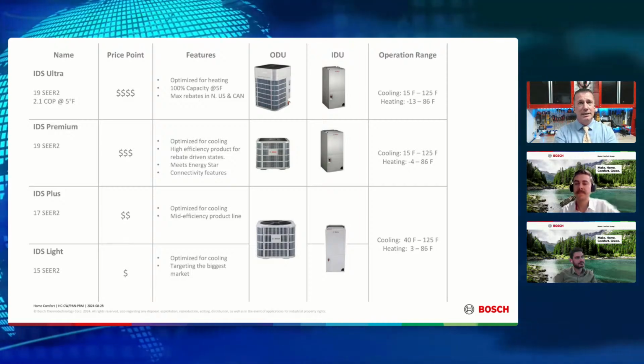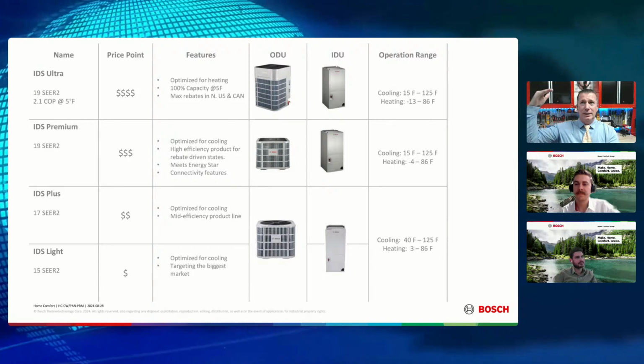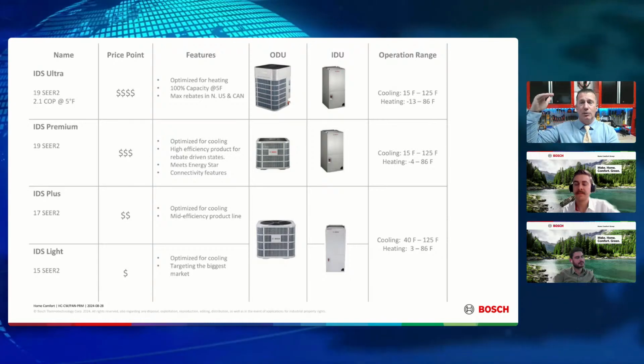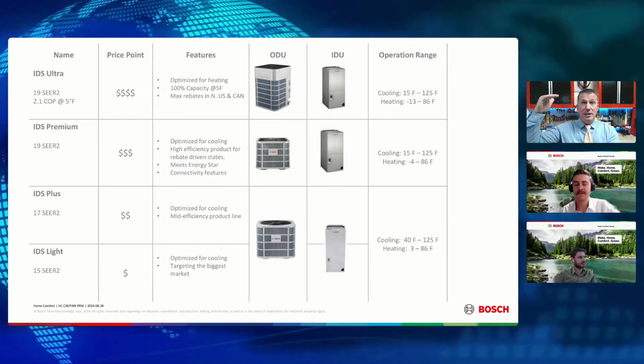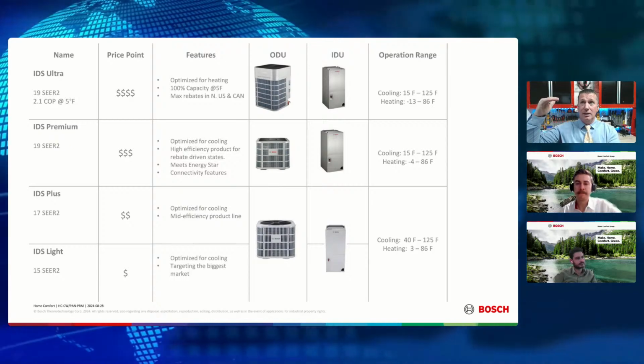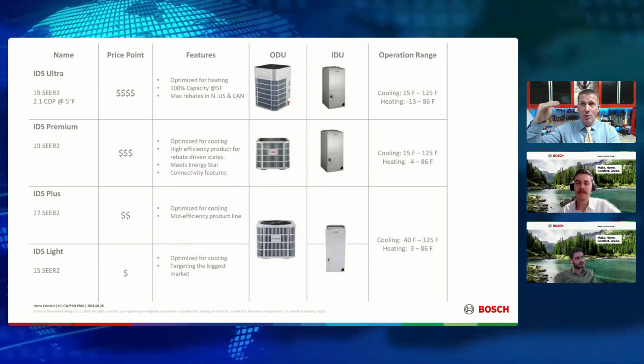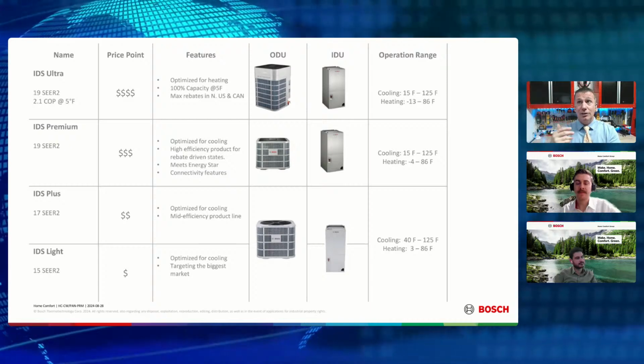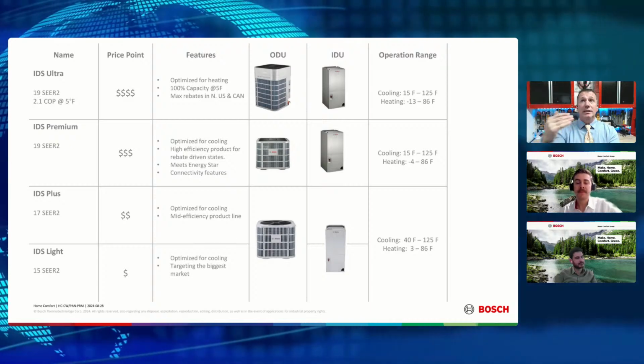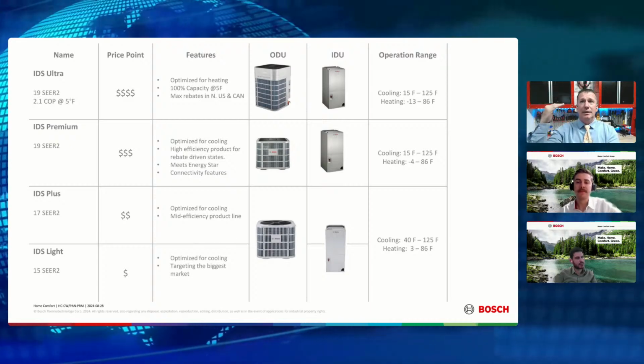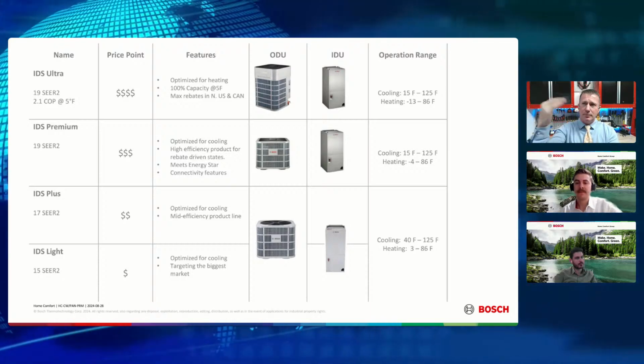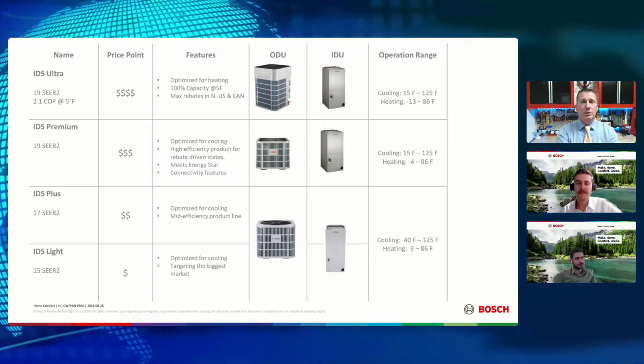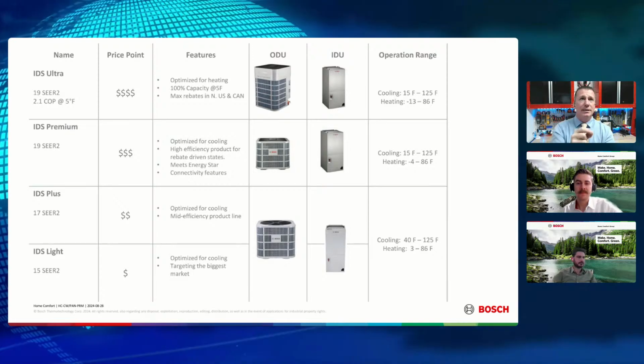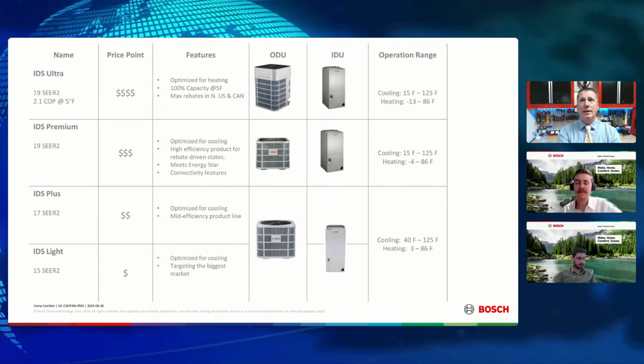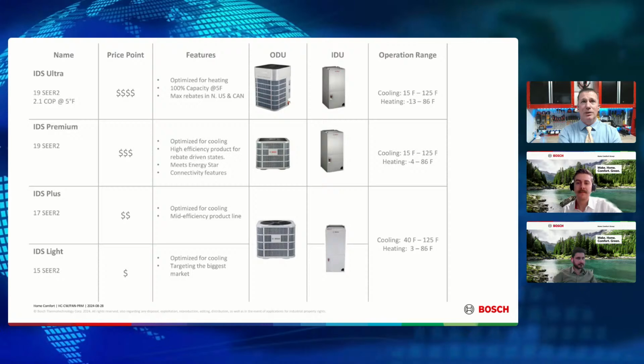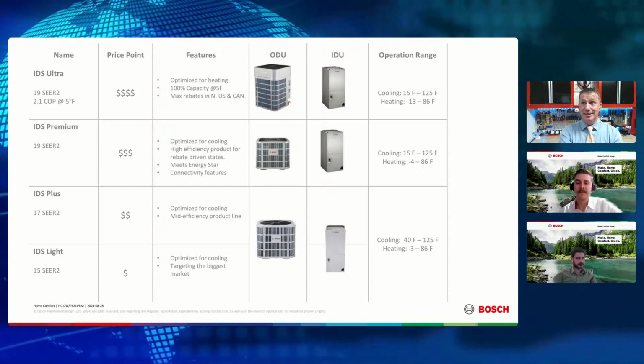When we start getting into inverter technology, I don't need to be running at 100% capacity at 47 degrees. So my BTU rating at 47 degrees may actually be significantly lower than it is at 15 degrees, because we can start re-ramping that compressor to meet the actual BTU loads that we need. So when we look at those extended heating data tables, don't be a bit surprised to see more heating capability at 5 degrees than you have at 47 degrees.